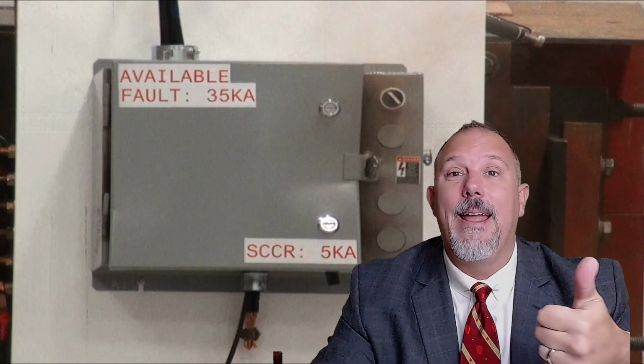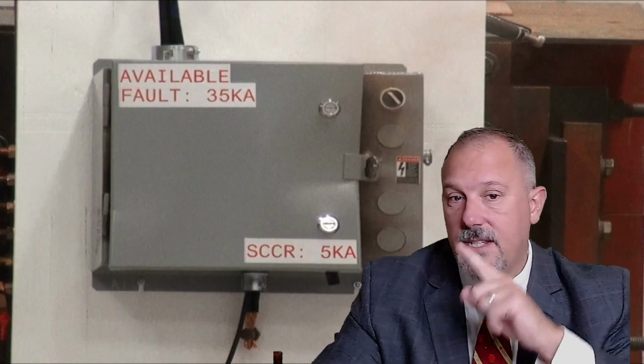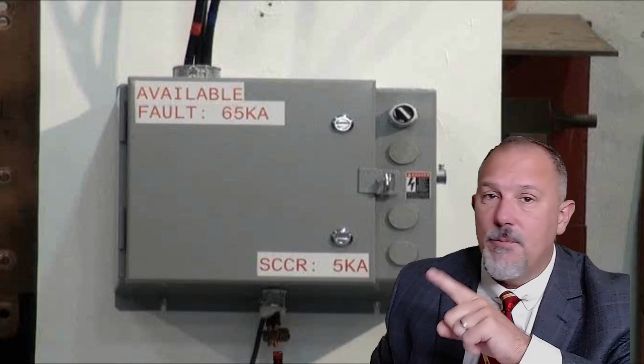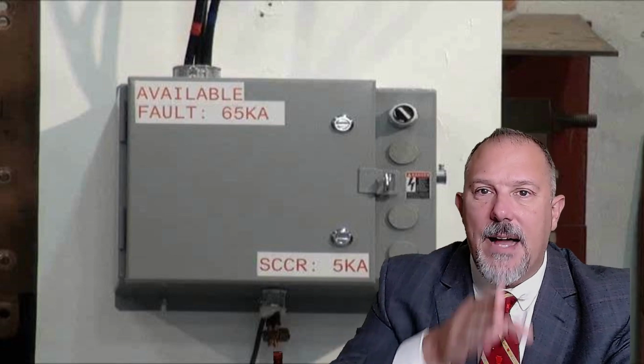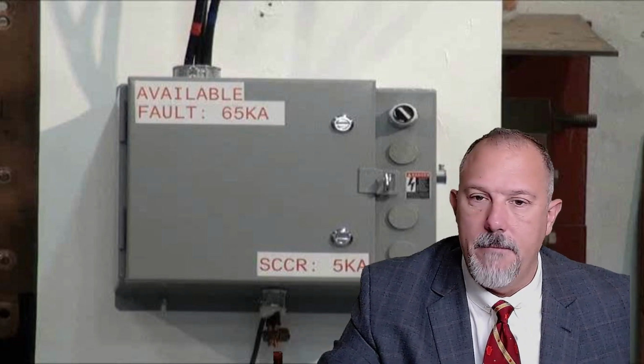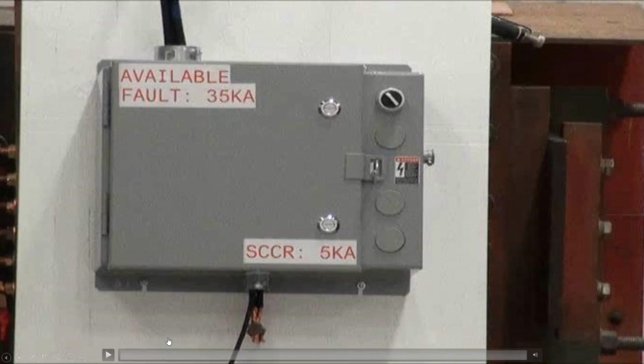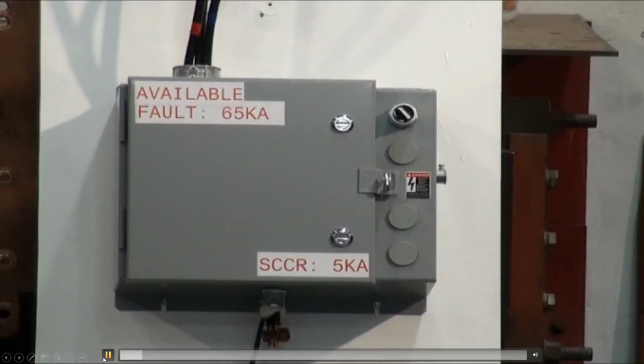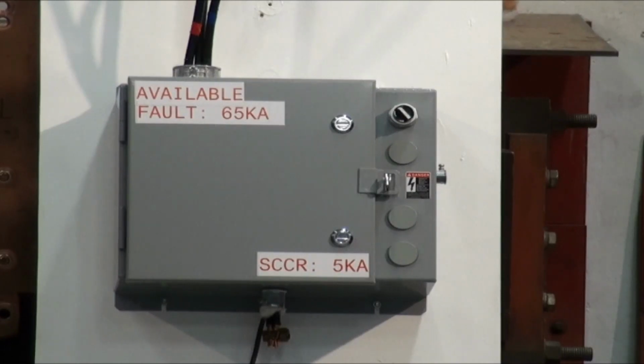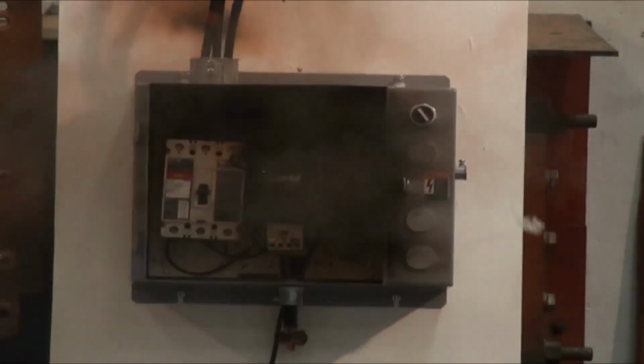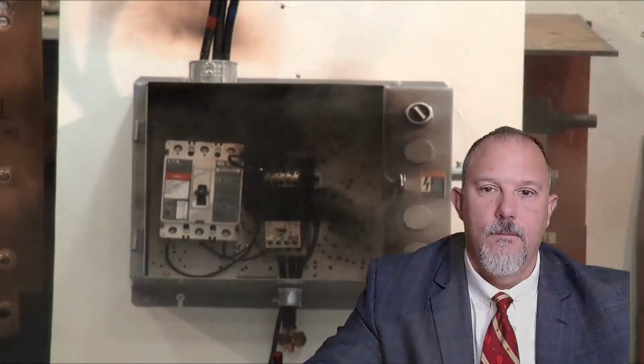Now we're going to up the ante here. We're going to increase that fault current with the same rated equipment. This is still a 5,000 amp short circuit current rated equipment. I'm going to let 65,000 amps pass through this piece of equipment. Whoa. So when you exceed the ratings of equipment, that door went about 25 feet in the lab. That is a severe misapplication of this equipment.